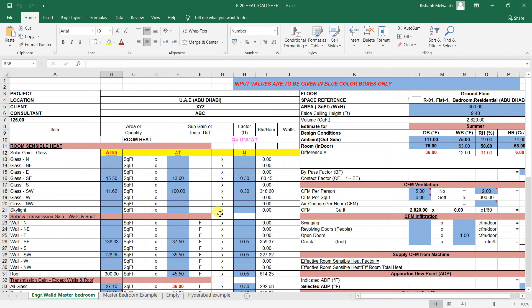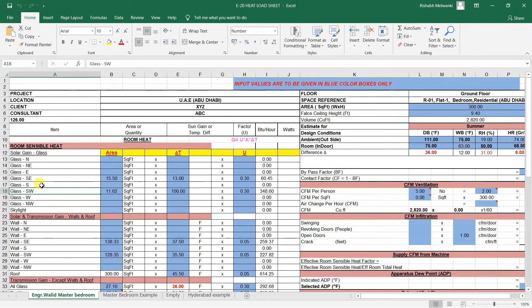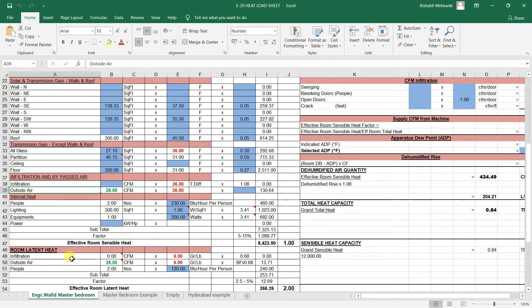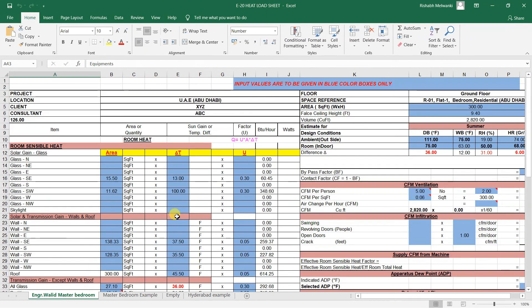In the Excel E20 form, different glass orientations are given — north, northeast, east, southeast — and wherever we have a window and glass, according to that we consider the load. We also have walls, infiltration, outside air, ventilation, people, lighting, equipment, and other things. Based on this we calculate the CFM — cubic feet per minute — which is the flow rate of air required. This data, using the E20 form, forms the basis of duct design calculation.